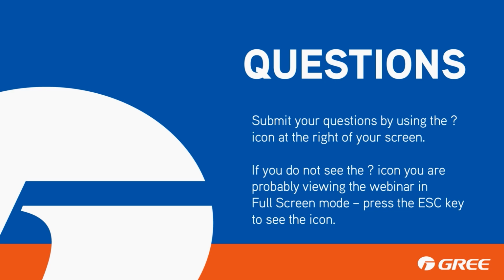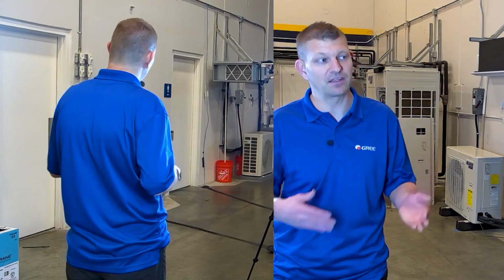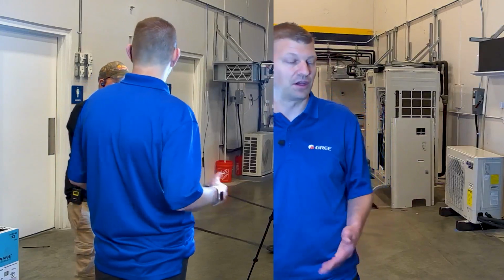Well, I'm not against a bypass. I'll disagree with you there. Okay. And that's all. It's okay. Everybody has their own views. My thought process is I don't want a zone less than 50%. Correct. Yeah. And then you've got to make sure you're getting proper bypass or a dump zone on this, so the static pressure doesn't get too high across the system. And when you install it, be sure to shut down each zone and check your static and make sure we're below where we need to be.